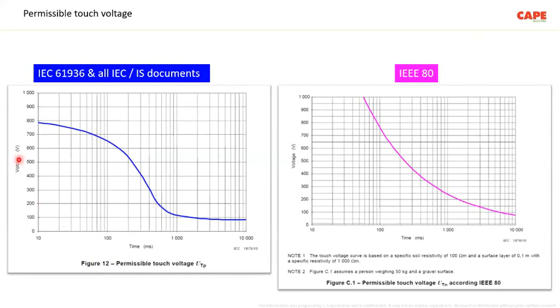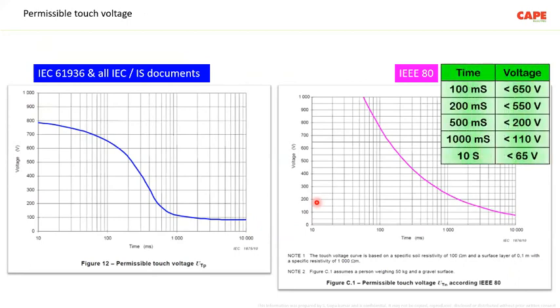The touch voltages, the IEC way, IEC 61936, explains the permissible touch voltage. You can also find this chart table in IS 732. The permissible touch voltage followed in IEC and IEEE shows a little bit of difference, but practically both are almost the same. What IEC recommends is a fault of less than or equal to 65 volt, or within 10 seconds the touch voltage must be reduced to 65 volt.